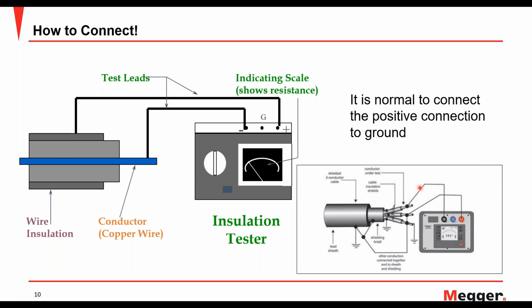But just make sure that whatever is under test, everything else is hooked up to the positive terminal or negative terminal, depending on how you are connecting it, and everything else is grounded other than the object under test. Most of the time, there's a third terminal, the blue one, which is the guard terminal. A lot of people don't know the use of the guard terminal, and I will cover a little bit further in my presentation what exactly it is used for. Usually it's a blue lead that you get with your Megger test set, and most of the time people don't know what it is for, or it's just there and never used. I will cover when you need to use that.